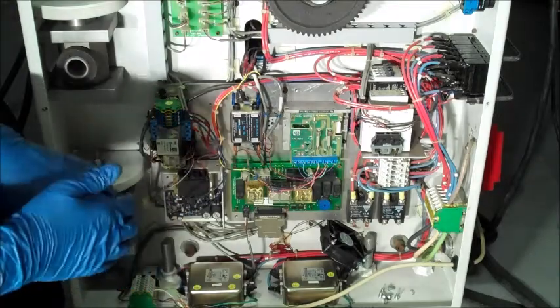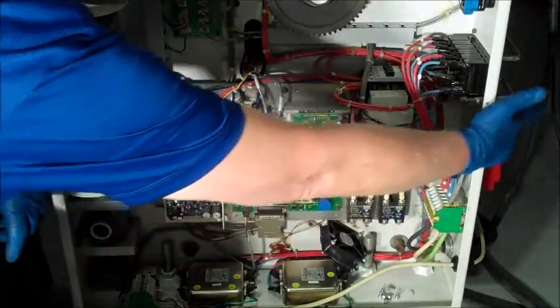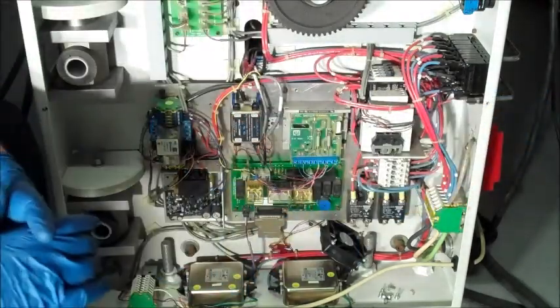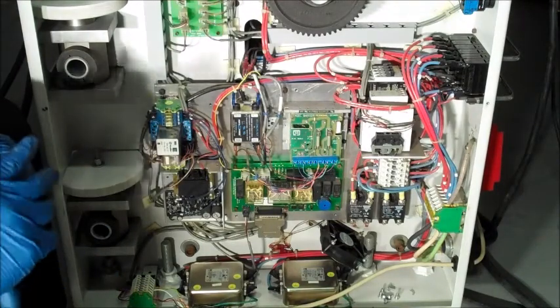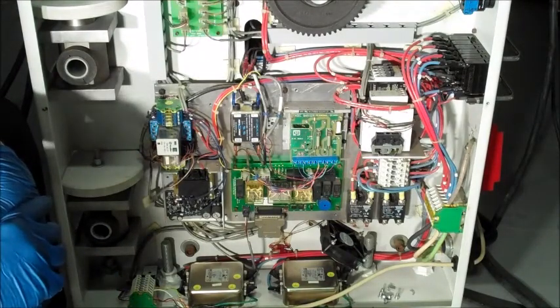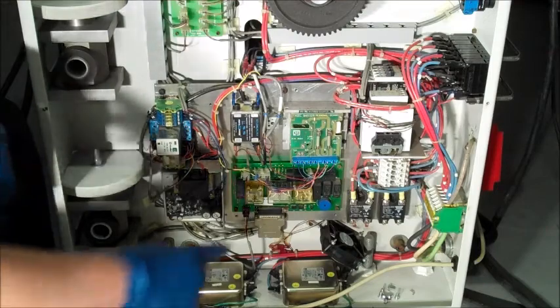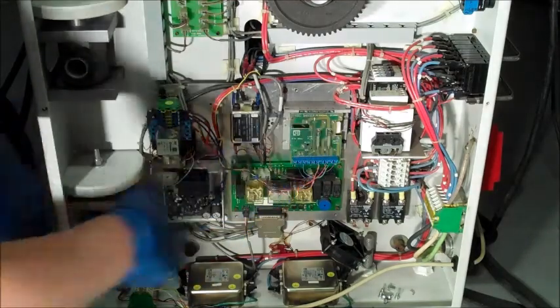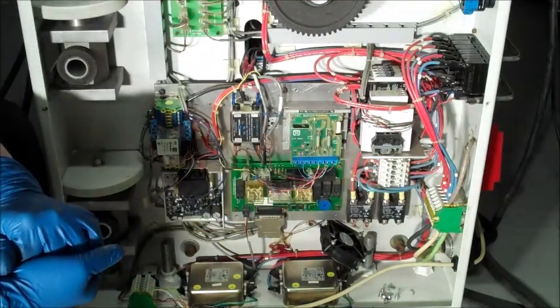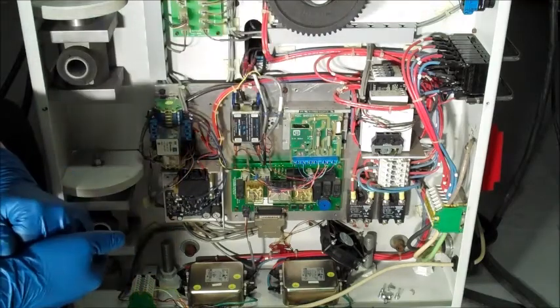You also are going to have some fuses that run along the back side of the machine. Those usually have to do with the motor. They're actually kind of redundant on this. They've got motor fuses on the KBIC board and also on the back of the machine.